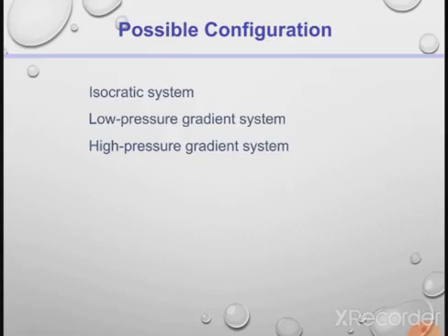Since it is mixed prior to the pump, it is called the low pressure gradient system, because at that time the mixing pressure is very low, before the pump.